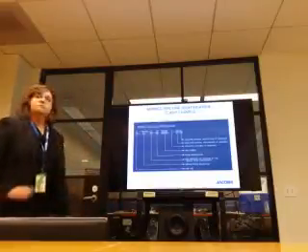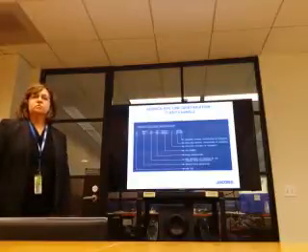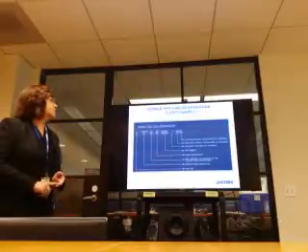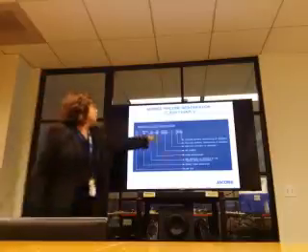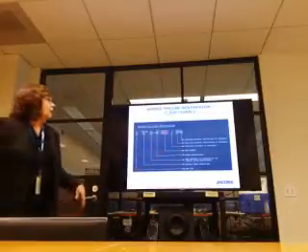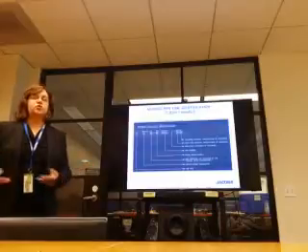They have a unique 7-digit line number that only appears on the one line. And then they have a 3-digit insulation code that tells you the thickness of the insulation that's appropriate for that service, for that pipe size. It tells you the insulation material, that's the 052. For example, it's fiberglass insulation on this pipe. And the last digit they have is the jacket. Sometimes we want a jacket over the insulation material for abuse protection or for cleanability. That happens to be a PVC jacket.